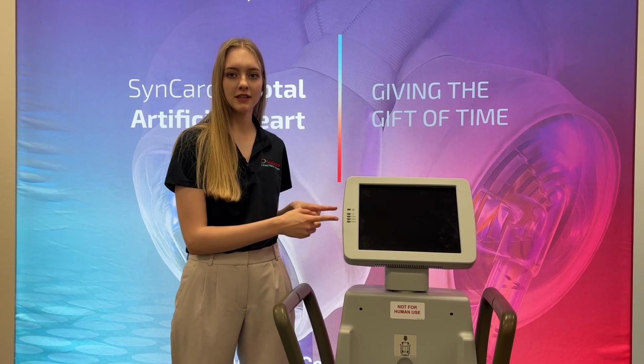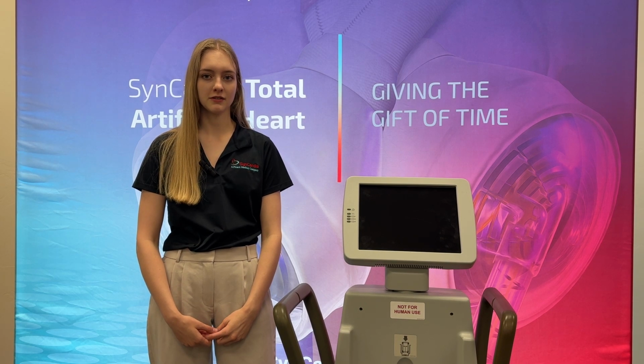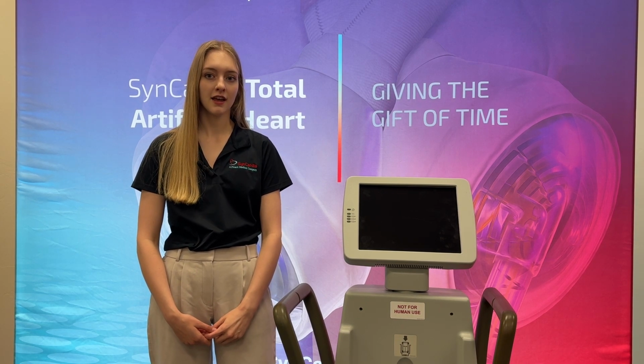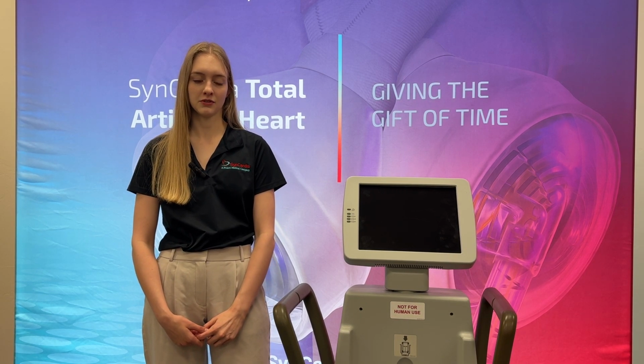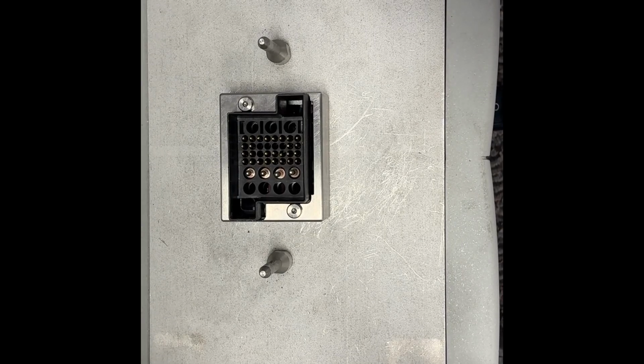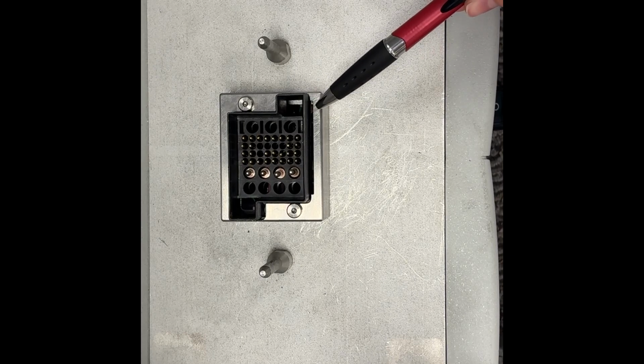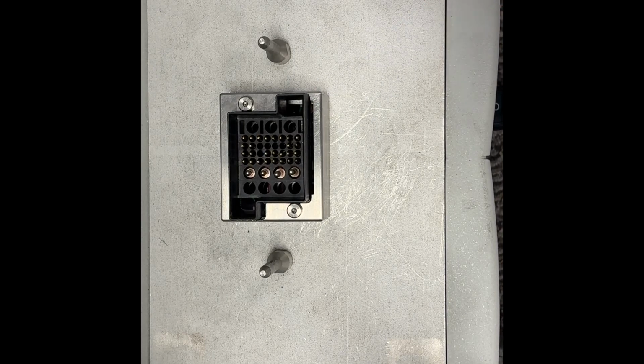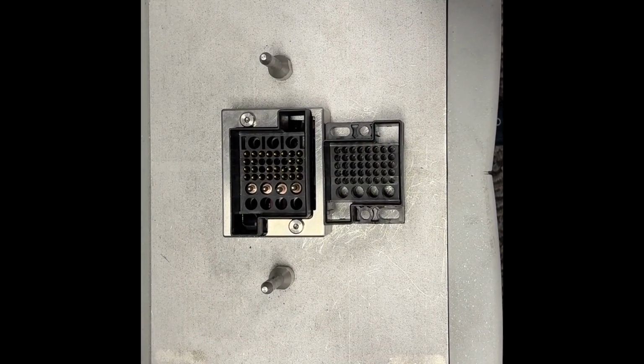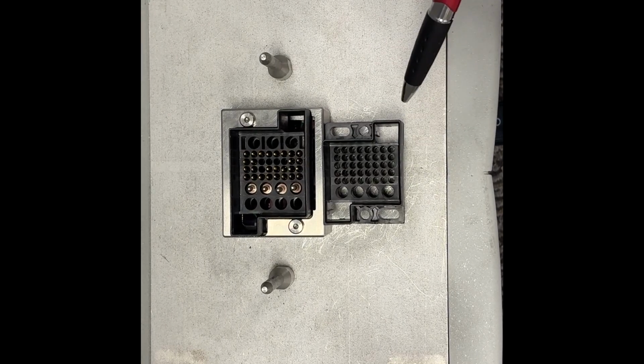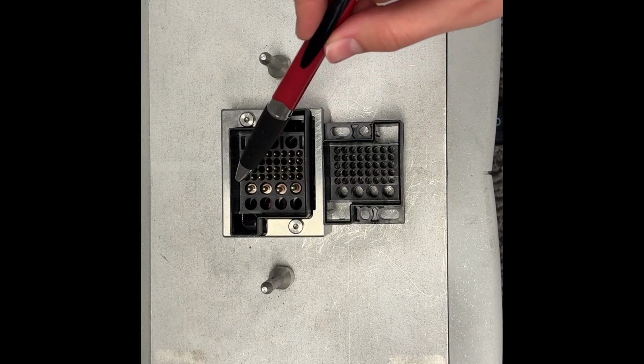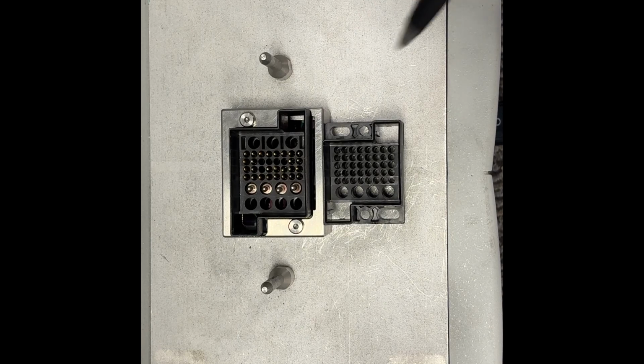The new display screen integrates into the existing hospital cart using the same data cable as the old screen and a modified converter cable from the old screen as well. The new connector is larger than the old connector, so we modified the housing part for the connector on the hospital cart and the C2 driver to fit our connector. The old obsolete connector has an 8x5 configuration of data pins, while the new connector has an 8x4 configuration of data pins. Both connectors use the same exact pins, so we reconfigured the pins from the old connector to the new connector.